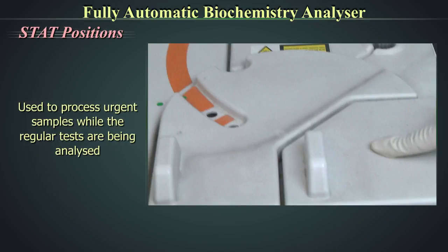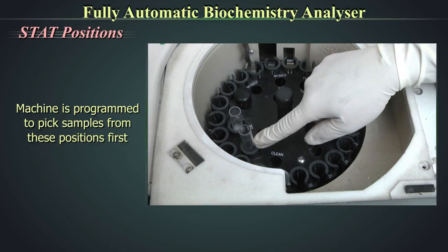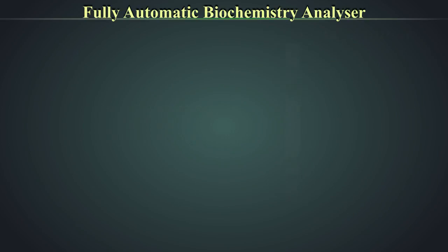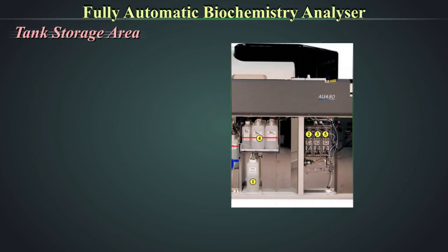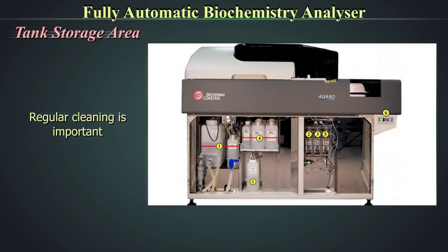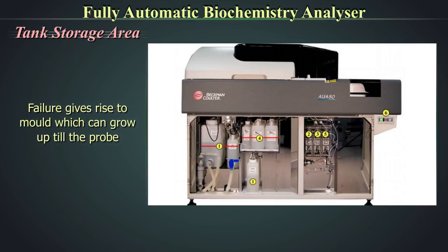Stat positions are used to process urgent samples while regular tests are being analyzed; the machine is programmed to pick samples from these positions first. The tank storage area houses the deionized water tank, wash solution tank, and diluted wash solution tank used to clean cuvettes, mix bars, and the rinse component. Regular cleaning of this water tank and filters is very important, as failure to do so may give rise to mold which can grow up to the probes.